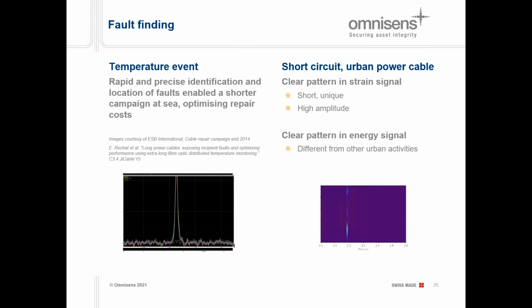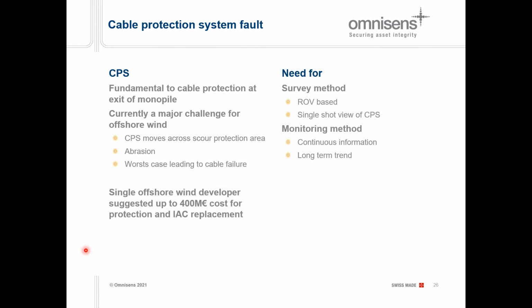I also mentioned the possibility of looking at the cable protection system. CPS are fundamental to protect the cable where it exits the monopile inside the array. There is currently a major challenge for the offshore wind industry, as some CPS are moving across the scour protection area. There's abrasion, and in some cases failure. One developer suggested a cost of a couple hundred million euros for replacement of interarray cable due to these issues.